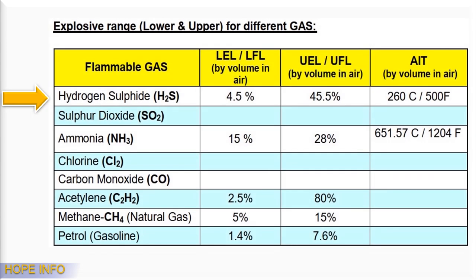Explosive range — lower and upper — for different gases: Hydrogen sulfide (H2S): LEL 4.5%, UEL 45.5%. Sulfur dioxide (SO2). Ammonia (NH3): LEL 15%, UEL 28%. Chlorine (Cl2). Carbon monoxide (CO). Acetylene (C2H2): LEL 2.5%, UEL 80%. Methane (CH4) or natural gas: LEL 5%, UEL 15%. Petrol or gasoline: LEL 1.4%, UEL 7.6%.